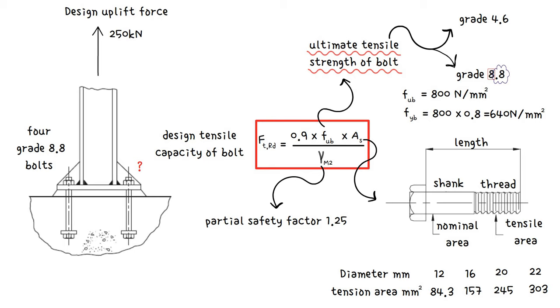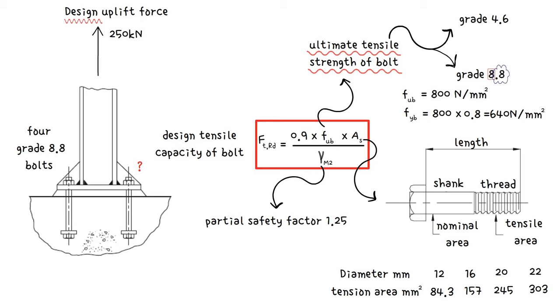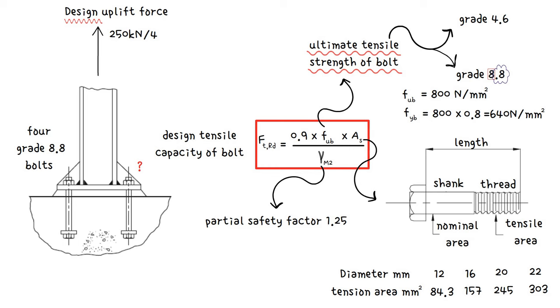Bear in mind, the uplift load 250 kN is stated as the design force and hence already includes partial safety factors for loads. So, load per bolt equals 250 kN divided by number of bolts, which is 4. This gives us a value of 62.5 kN.